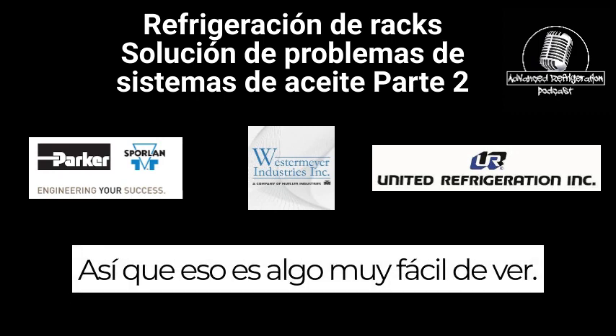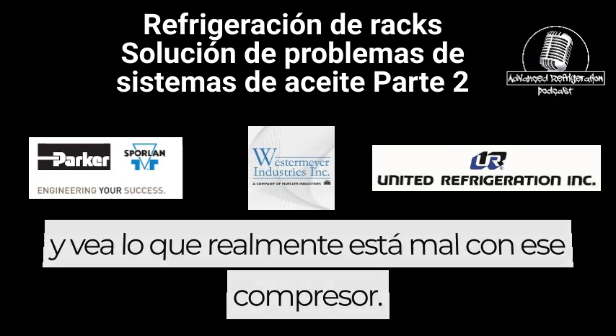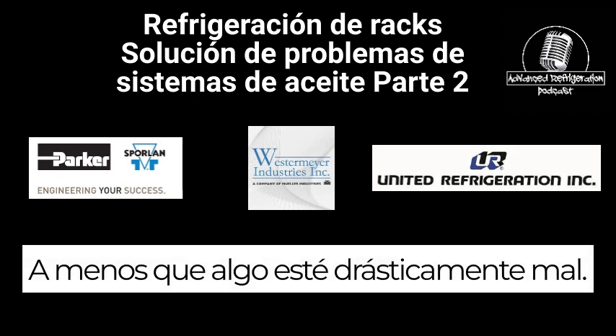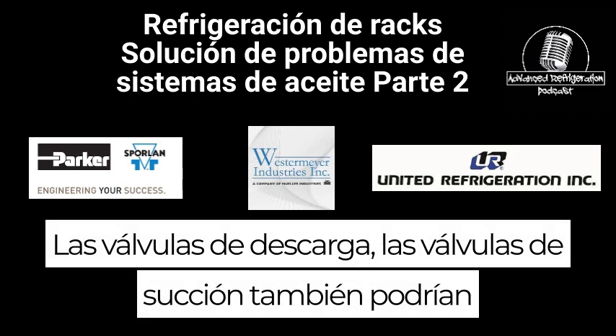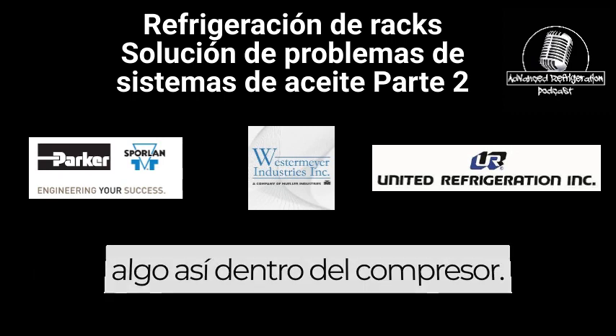So that's a very, very easy thing to look for. You're basically just looking for misting. At that point, you can do a pump down test and see what's actually wrong with that compressor. Unless something is drastically wrong, it could be discharge valves, suction valves, or you could have dropped the piston or something like that inside the compressor.